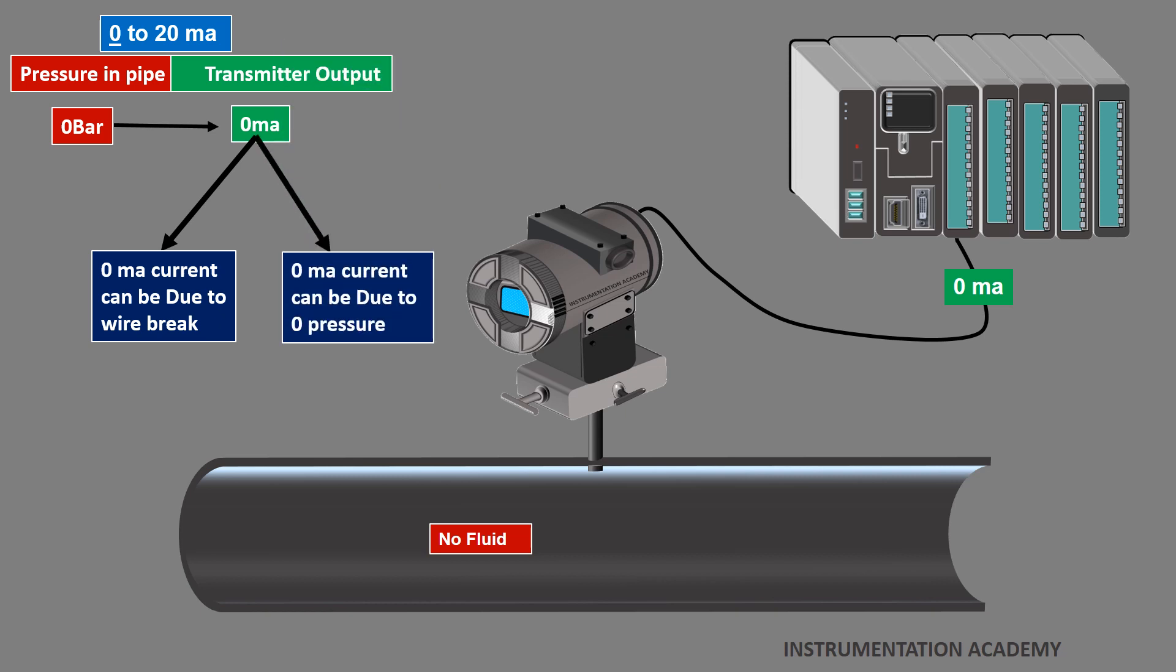Hence, if the transmitter is calibrated to generate current signal in the range of 4 to 20 mA, the faults like wire breaks can be easily detected. But this reason is a secondary reason for the widespread use of 4 to 20 mA signal.